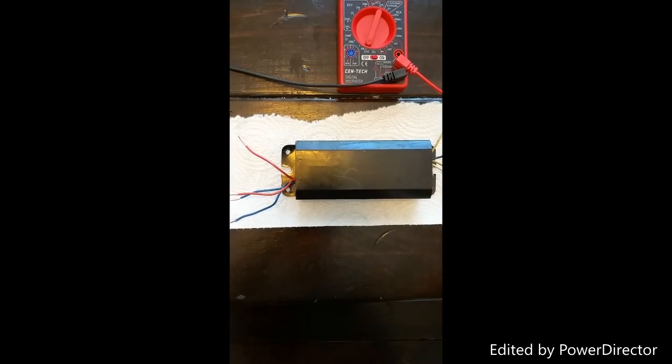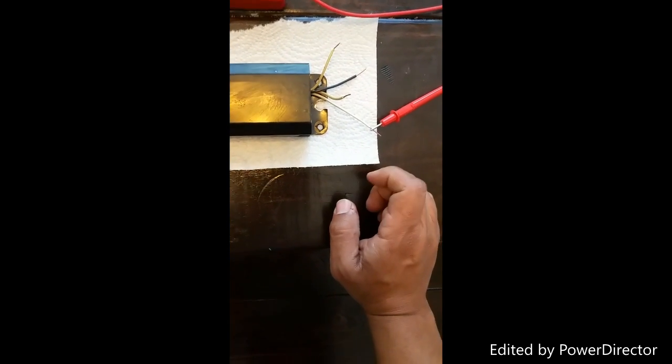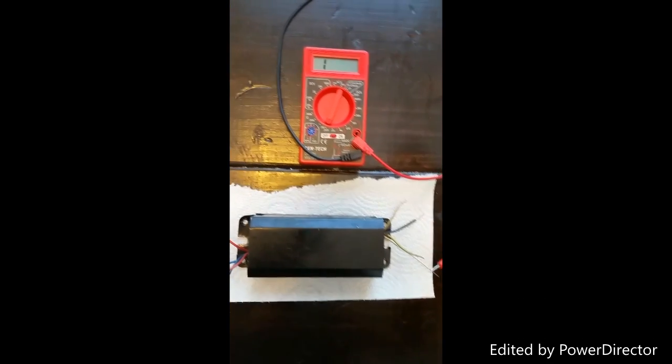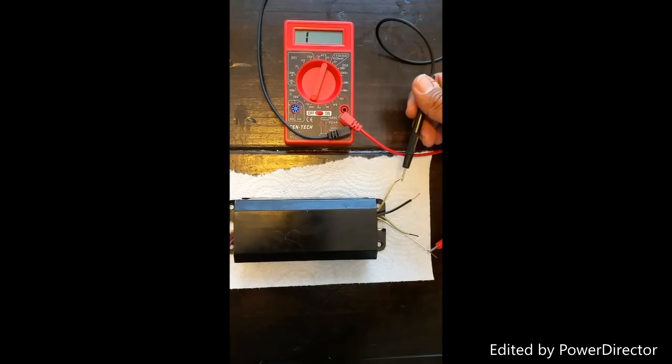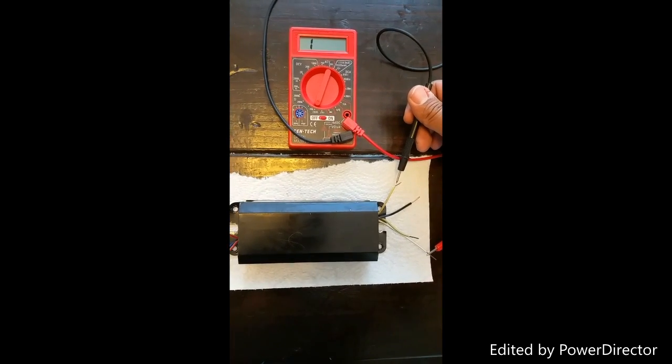You want to set one of your leads on the white wire - that's the power coming into the ballast - and then you take your other lead. Now if you see the gauge, you'll see what I'm talking about. I'm going to touch the yellow wire.